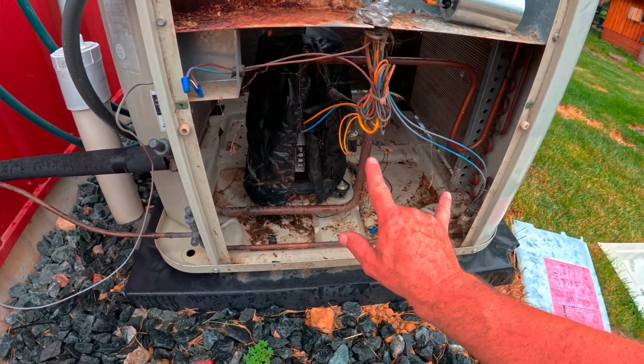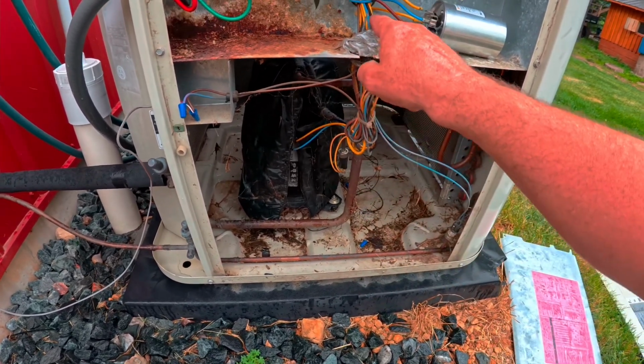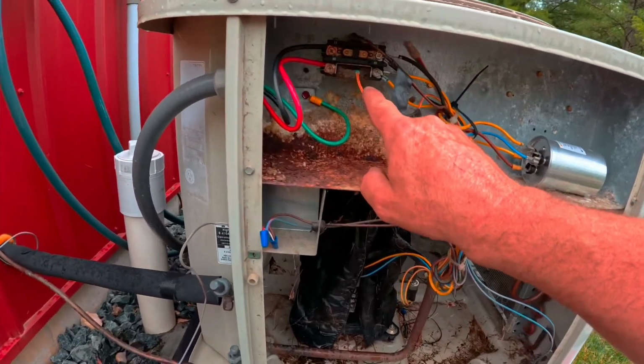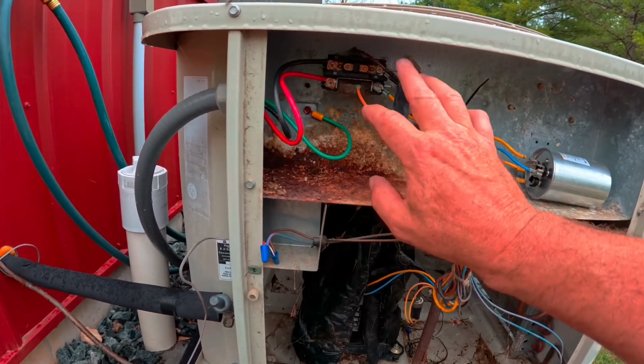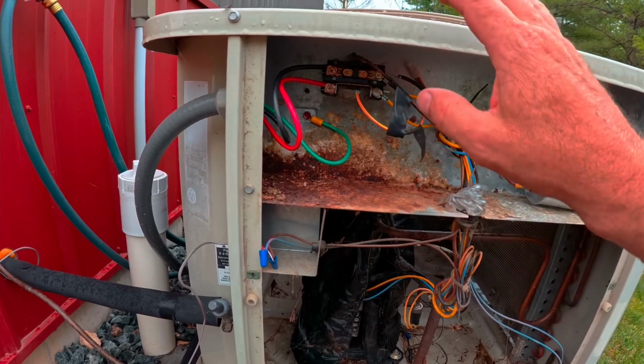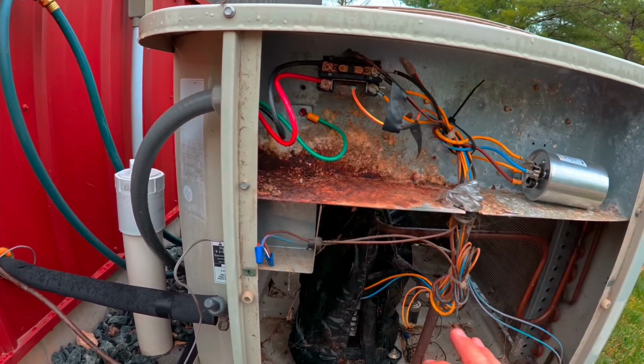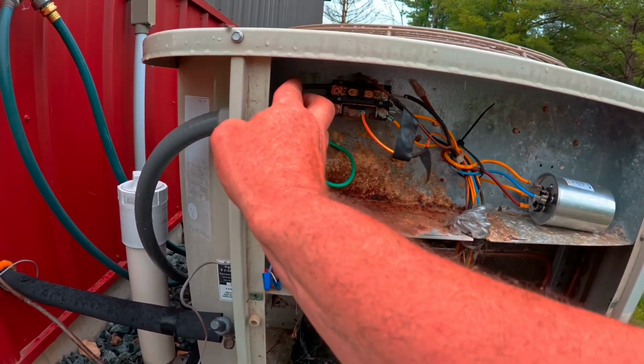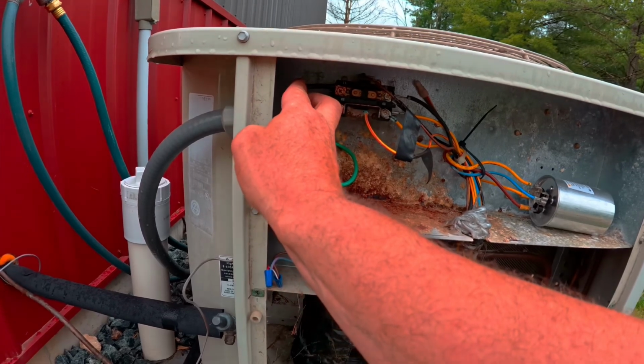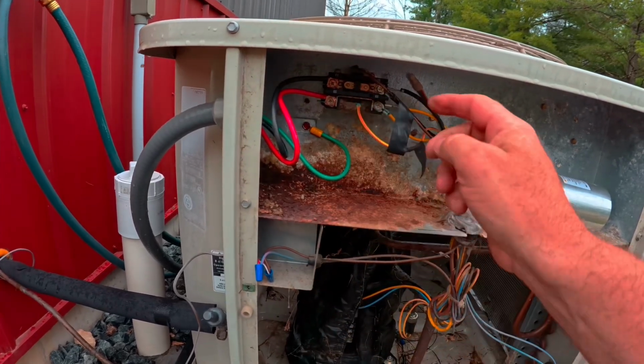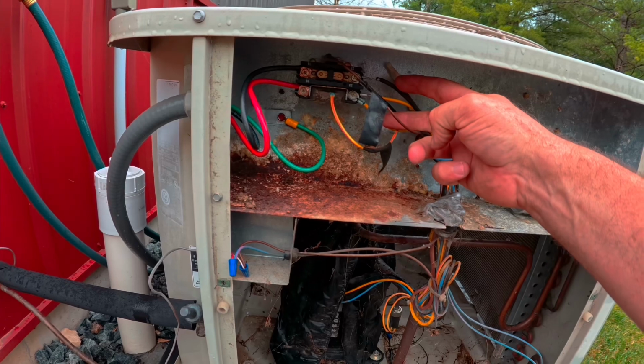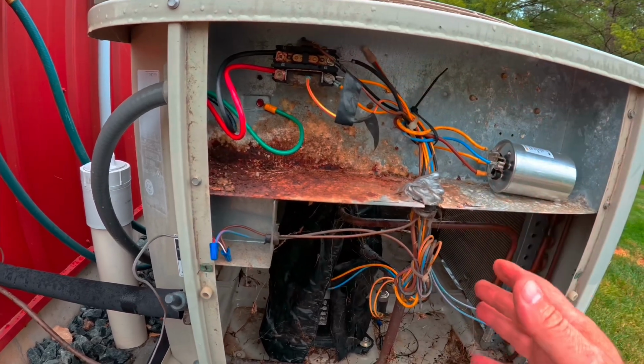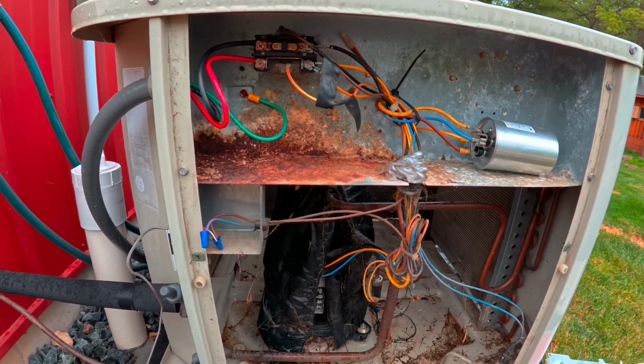and if both those switches are happy, then it's going to continue to send power up here to our main contactor. Now this is the main contactor that controls turning on the fan and the compressor. You got 240 volts coming in on one side, and then when the contactor closes, it sends 240 volts out the other side, which is obviously going to tell everybody to turn on. This is where most of our problems show up on a service call, right here at the contactor.